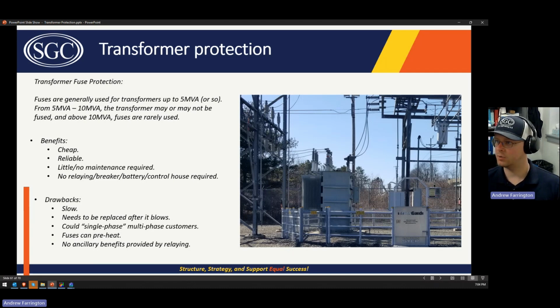If you have a fuse transformer like this one, you have distribution circuits coming out of the substation. If you have a fault, those reclosers are going to close into the fault multiple times. That's going to heat that fuse, and you need to account for that in your coordination study.